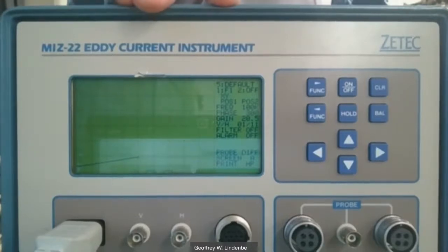This one only has adjustable gain. When we get to the newer unit, the 21B, that also has the ability to adjust the driver power, so how much power you're sending out to the coil. But this one does not. The 22 only has a fixed driver power. You can adjust frequency, and then you adjust the gain.